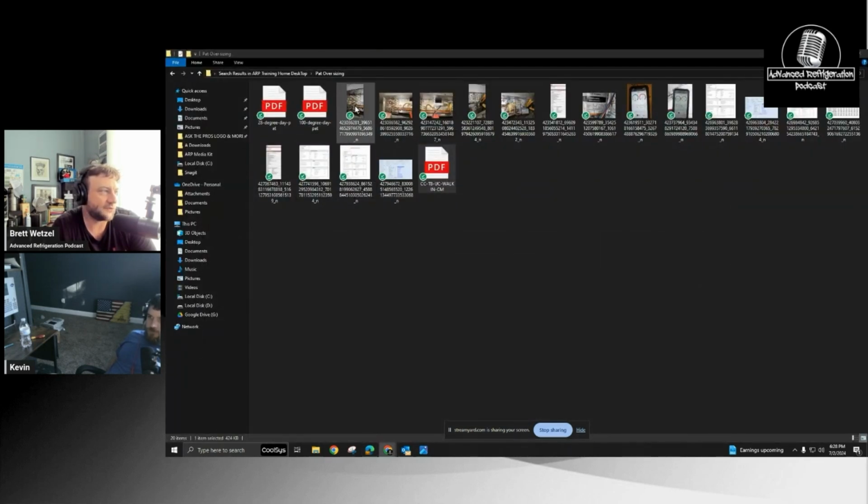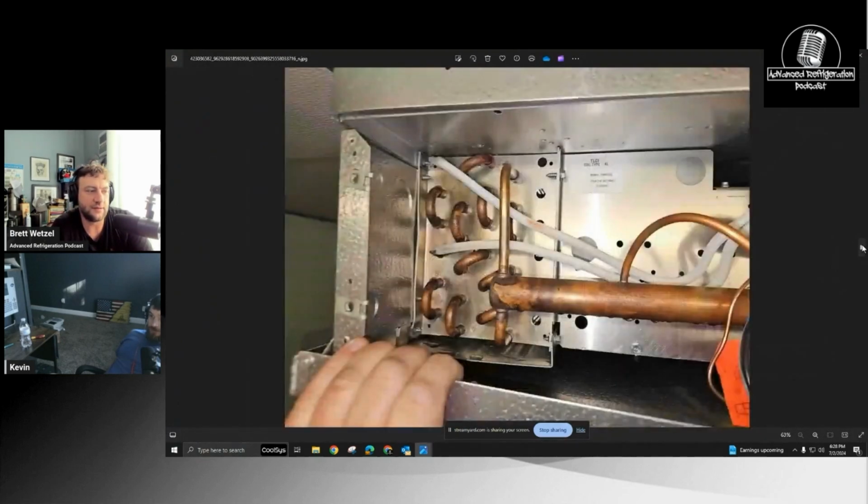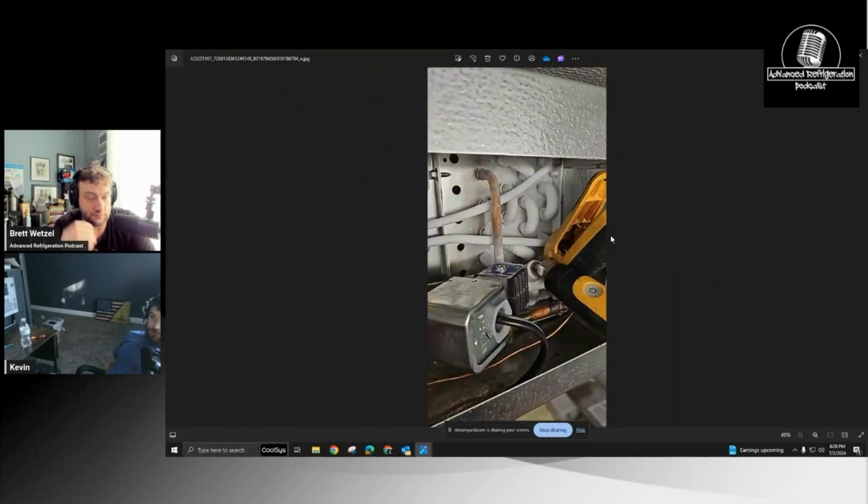So I had someone send me these pictures. It was the worst. The Bullseye store. Dry ambient room on the rack. Yes. And actually, the way that I figured this out one day, I had a produce area, the same area where you're talking about where they have the onions and the potatoes and stuff. I thought the expansion valve was bad, so I changed out the expansion valve for whatever the coil said. Let's just say it was a 10,000 BTU unit. I ended up putting a 1-ton cartridge in there. Not even close. Exactly. Because it has like a 20 or 30 degree TD.